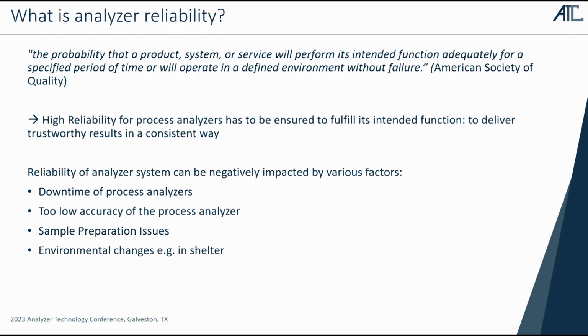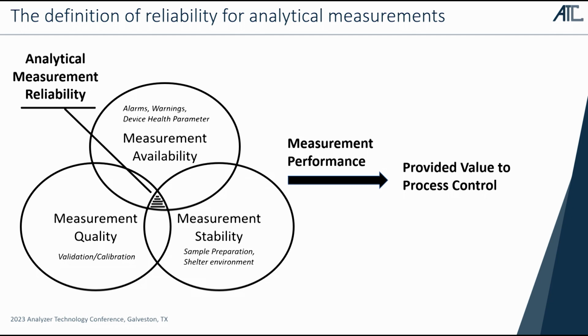It's not a device, it's a system consisting of many various elements, many various factors. So it's not only about the downtime of the process analyzer. It could be that the accuracy is too low. It could be that you have issues with sample preparation. Your shelter conditions are not stable, so the ambient pressure is changing. So it's all influencing the reliability of analytical measurements.